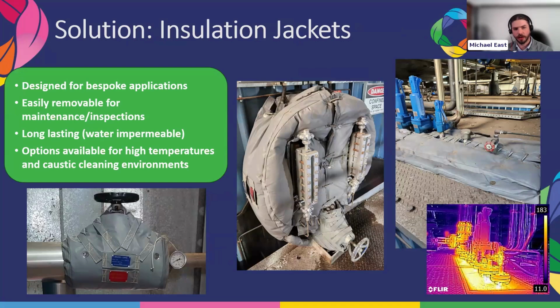So what does the solution look like? A lot of the reason they're not insulated is they're odd-shaped components, or you're putting rigid cladding on, and you can't just go straight over the top of a flange. What we've found is, probably 95% of the time, the solution is a flexible jacket like these examples. You can have fairly standard sizes to go around your nominal, say, 4-inch valve, but you can also make them very bespoke, designed for exactly one application - like in the middle there, where we've got the end of a drum on a boiler, and we've designed the jacket so you've still got the sight glasses sticking out and exposed, so you still meet all your boiler regulations and requirements, but we've cut down on the thermal losses coming out of there.